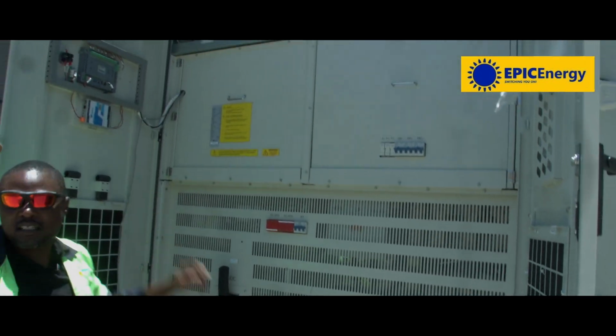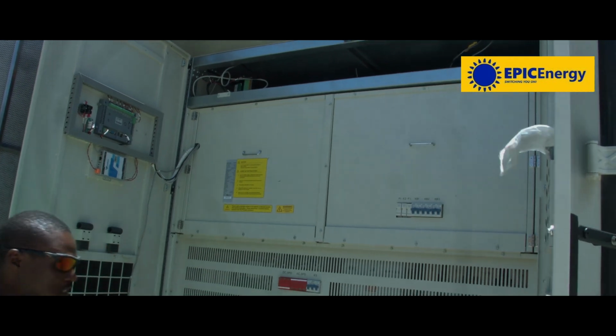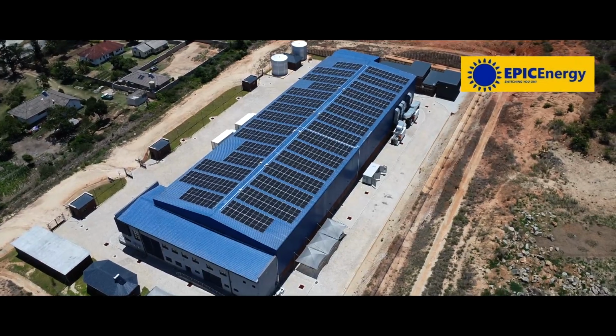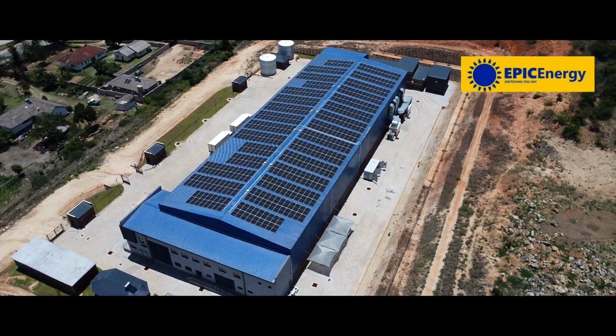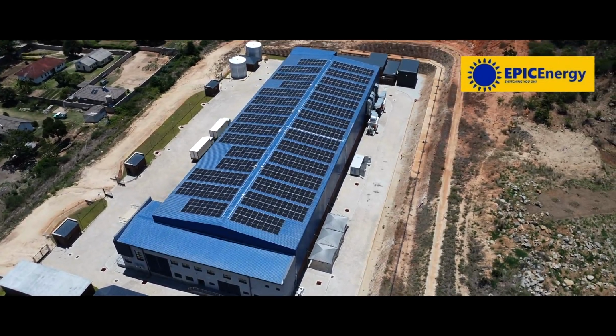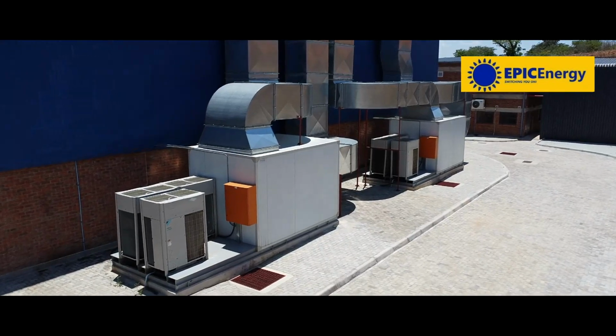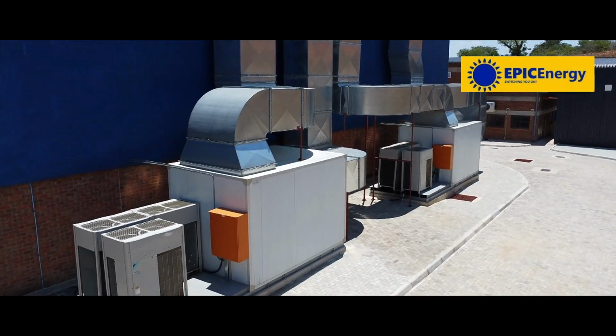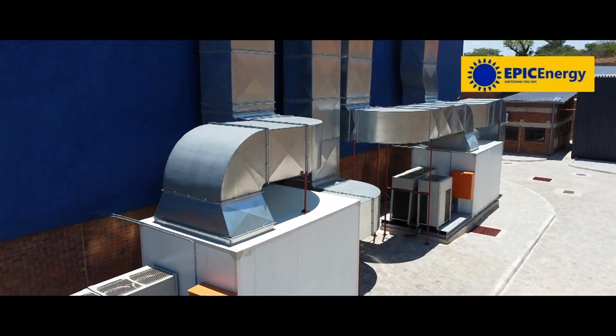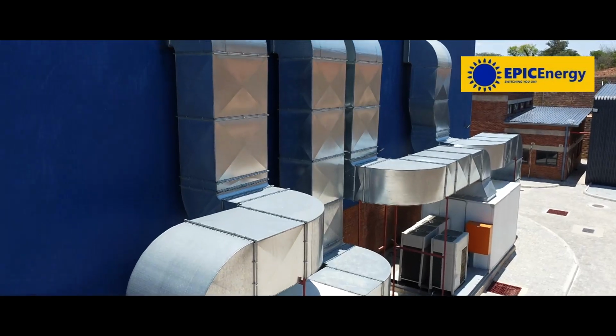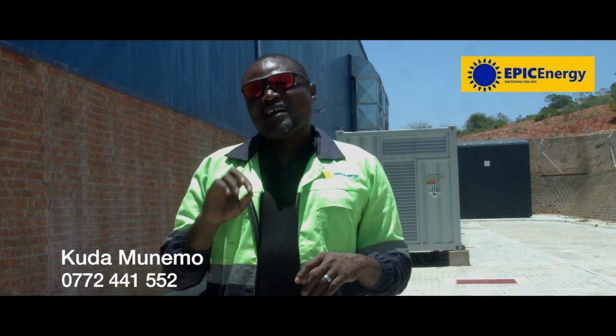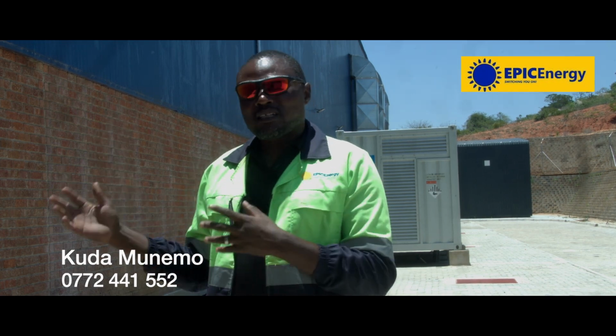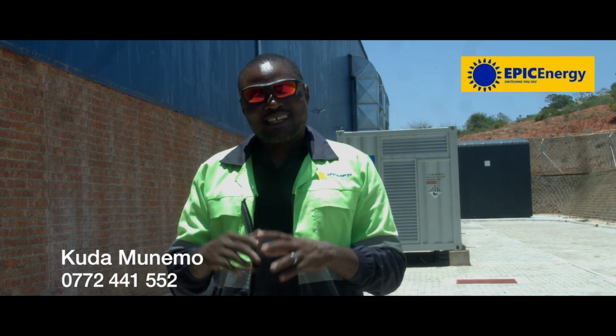Like I said, we have a 500 kilowatt inverter installed at this particular system, and it's powering the entire warehouse, which includes the air conditioning system, cold rooms, the HVAC, and also the fire suppression system for this entire unit. This means if there's no grid, they can run overnight without any issues through the battery bank that is available. The maximum load that they can put on the battery is around 50 kilowatts, which is the load operating the fire suppression system and the HVAC that cools down the entire space where we are.